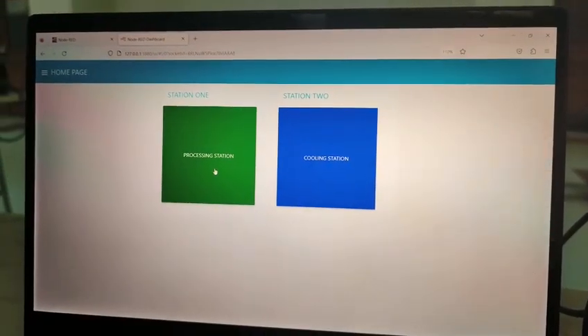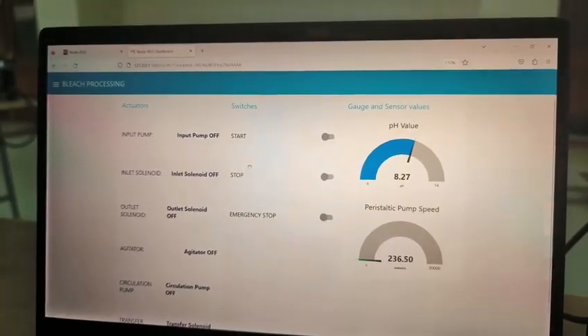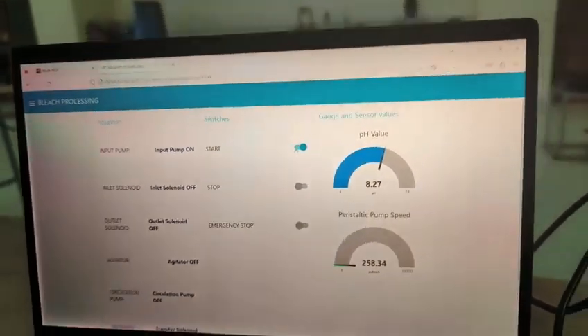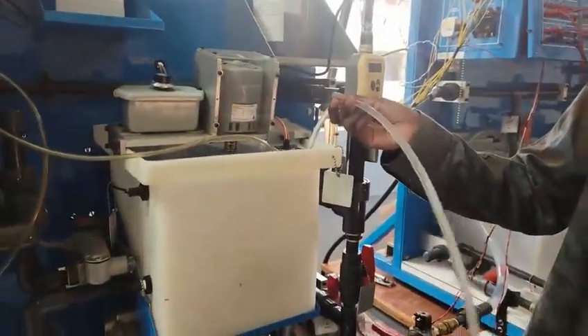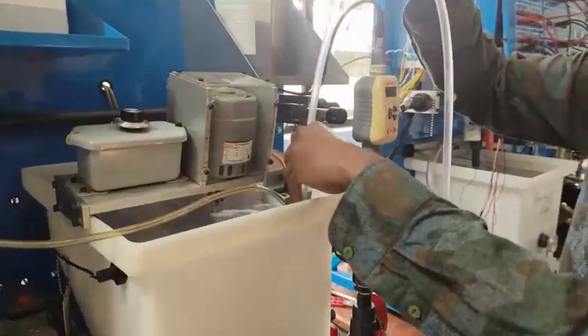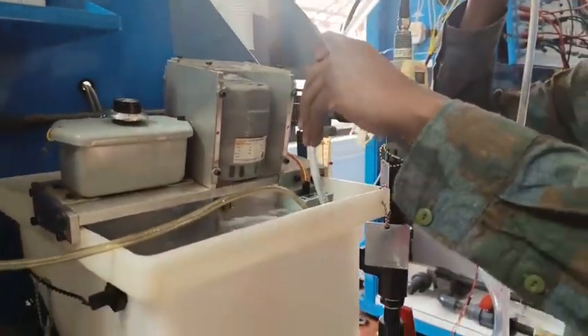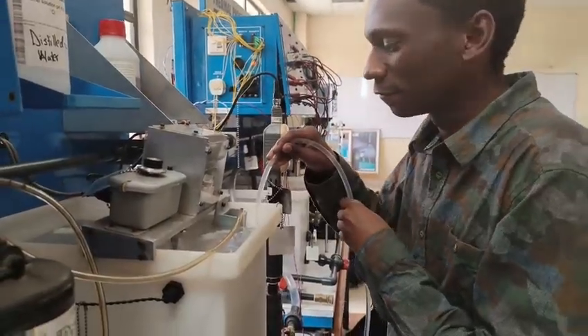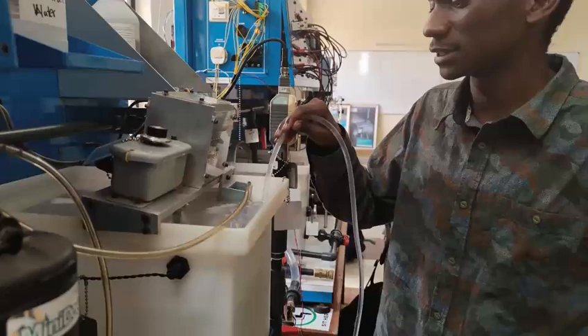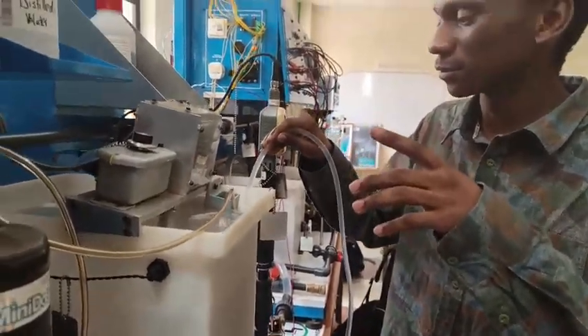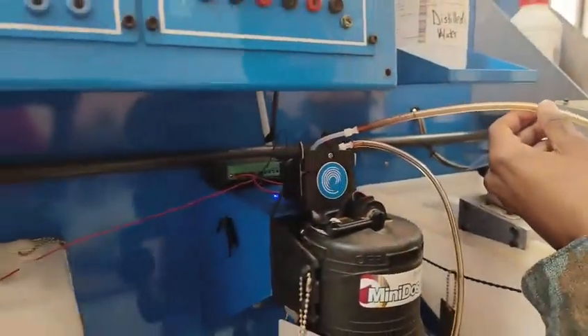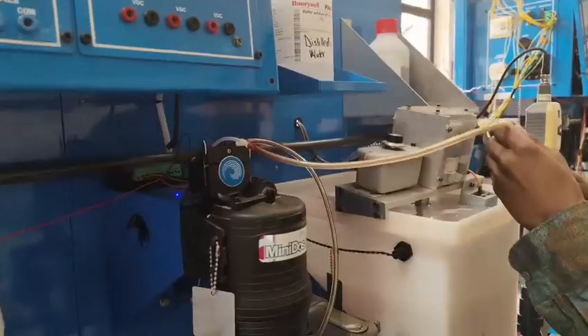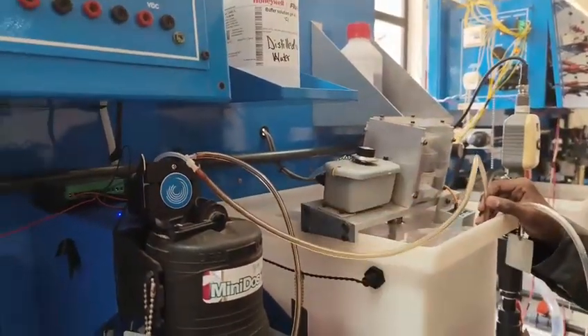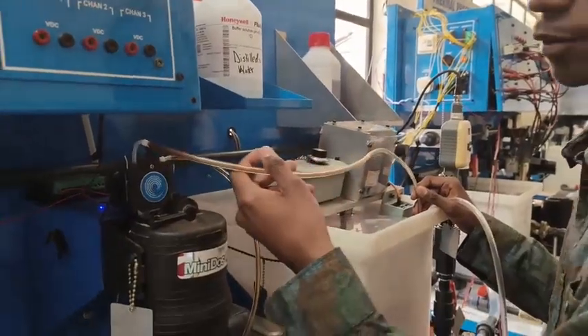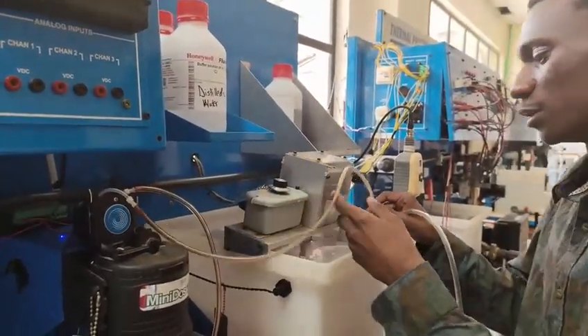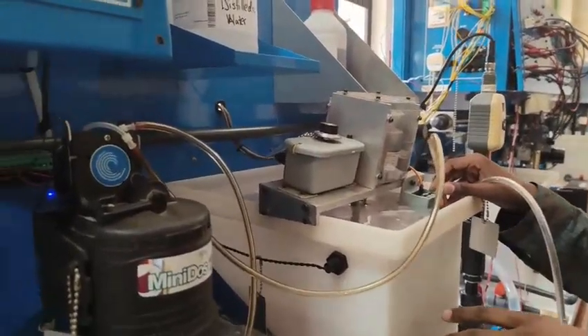So on the SCADA, the operator is able to navigate to the processing station and start the process. As you can see, the input pump is turned on in the SCADA and it starts pumping in the distilled water. The filling takes quite some time, but once it reaches the required point, you can see the whole system starts and the pump starts rotating according to the logic of the PID. It starts pumping in the concentrated calcium hypochlorite solution, which will be diluted until we reach the required set point.